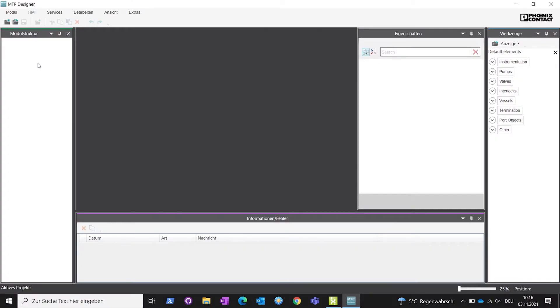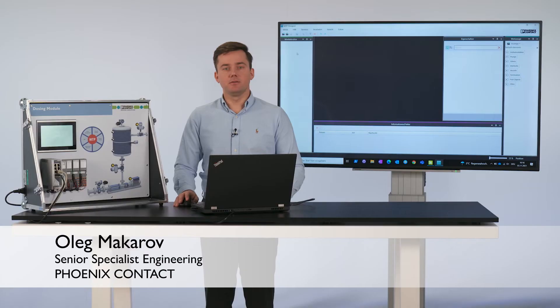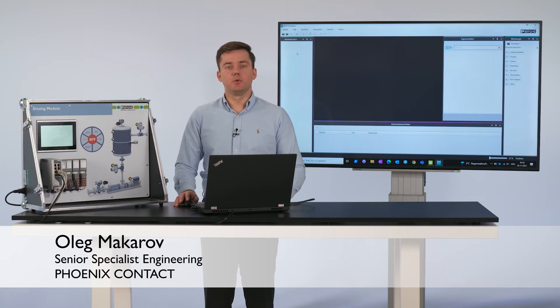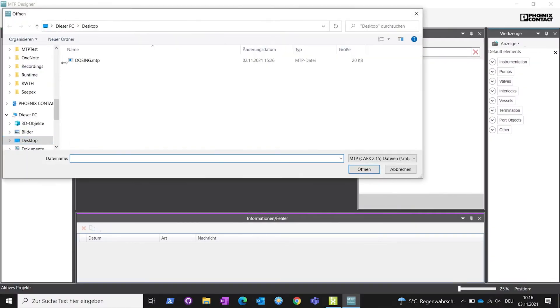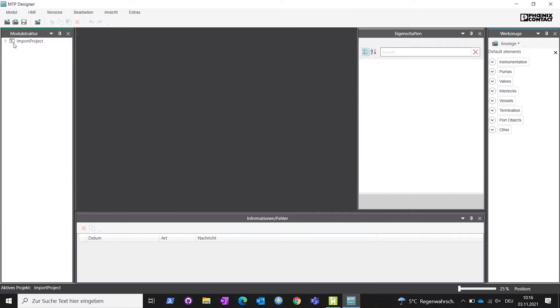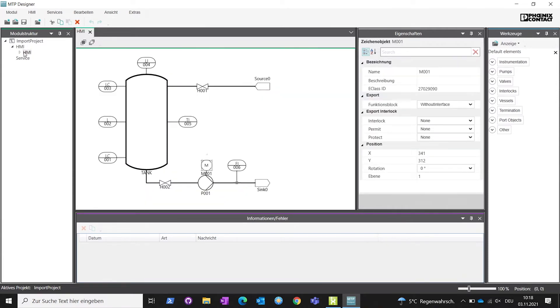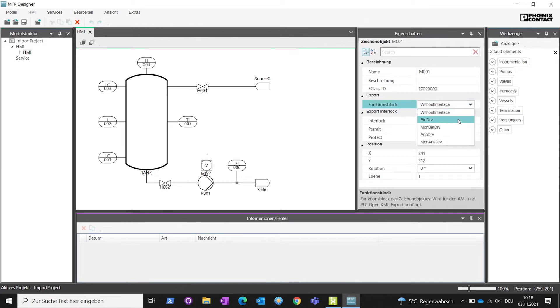Thank you very much, Niklas. Here we have the MTP Designer, a software tool from Phoenix Contact used not only to create and edit MTP files, but also to automatically generate SPS project bodies. I will show you how you can implement the module programming simply and cost-effectively. First, the file generated by X-Visual is imported into MTP Designer. The file is supplemented with information specific to Phoenix Contact — we can now define or adjust the interfaces which were not yet known at the start of system planning. For example, we can define a communication interface for the motor. In addition, we can define services and create additional procedures with just a few clicks. I will create a dosing service.